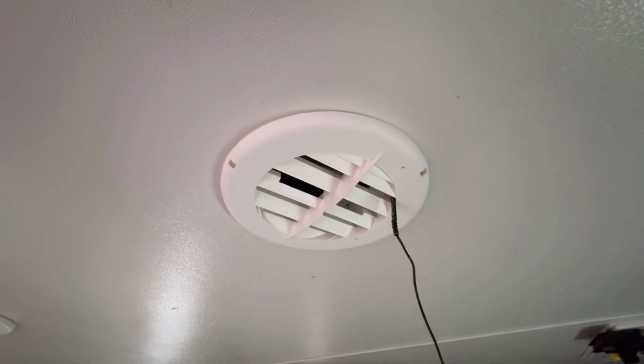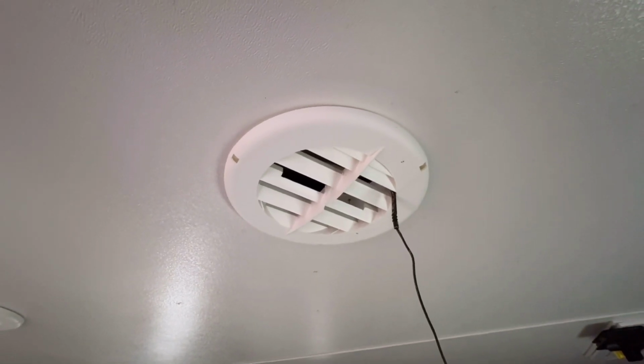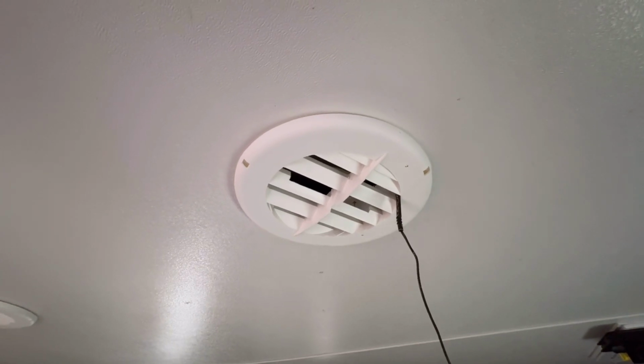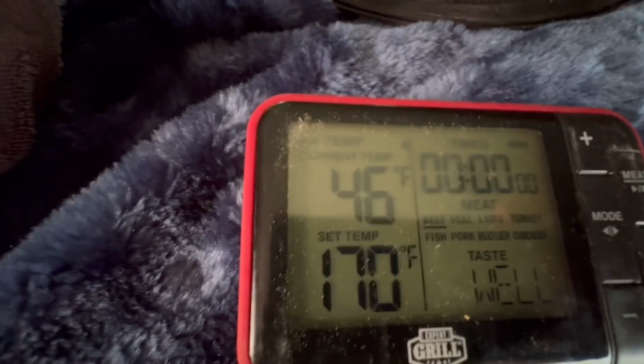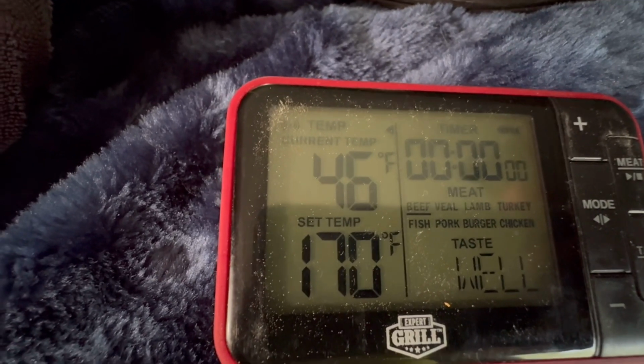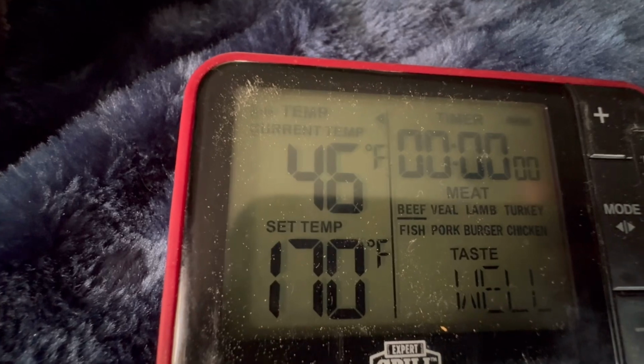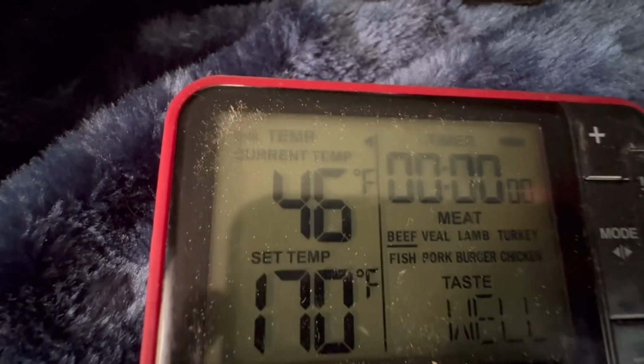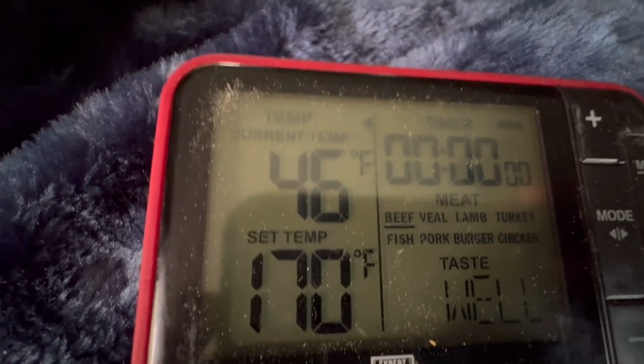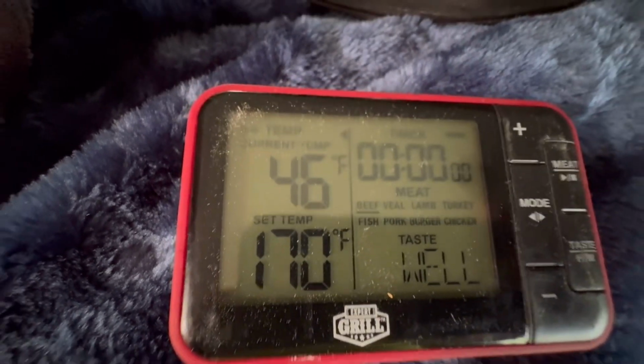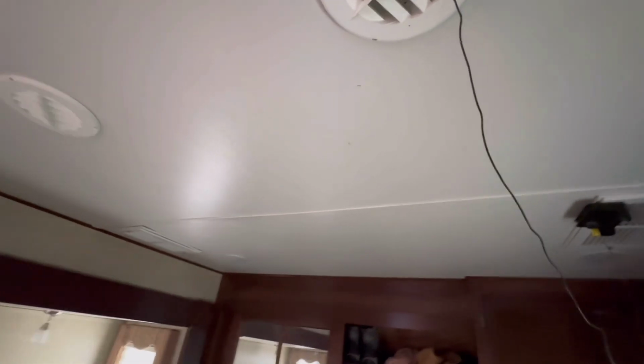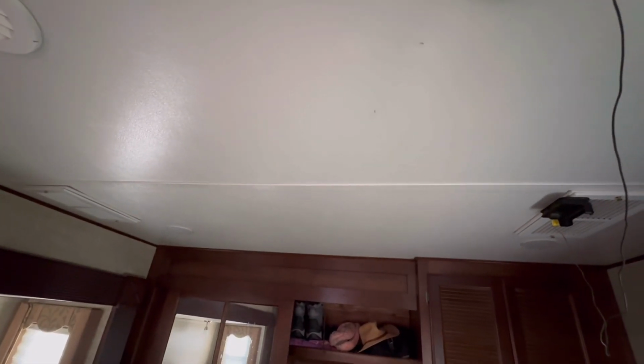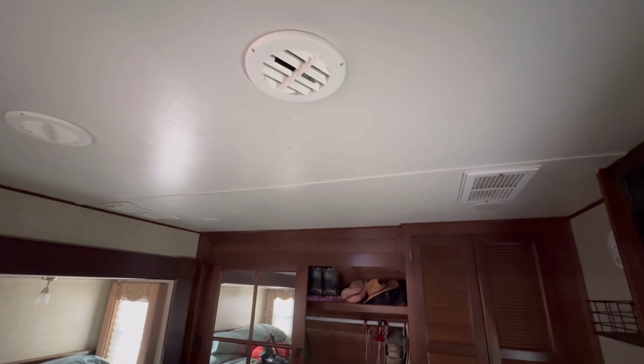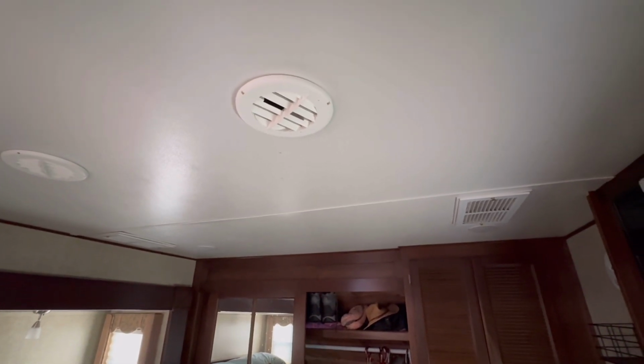Okay, you can see that I have the barbecue probe stuck up in one of the overhead outlets in the bedroom. Let's take a look and see what that temperature is. We're showing 46 degrees versus the 72 on the return. So what is that? About 26 degrees difference between the return grill and the output grill. So that tells me that the 12-year-old Penguin 2 AC unit is working very good. Okay, so we're still running the Zone 2 AC unit only.